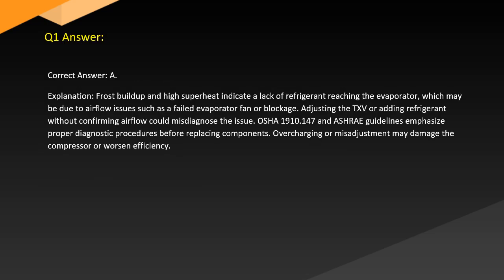Answer. Correct answer A. Explanation. Frost buildup and high superheat indicate a lack of refrigerant reaching the evaporator, which may be due to airflow issues such as a failed evaporator fan or blockage. Adjusting the TXV or adding refrigerant without confirming airflow could misdiagnose the issue. OSHA 1910.147 and ASHRAE guidelines emphasize proper diagnostic procedures before replacing components. Overcharging or misadjustment may damage the compressor or worsen efficiency.